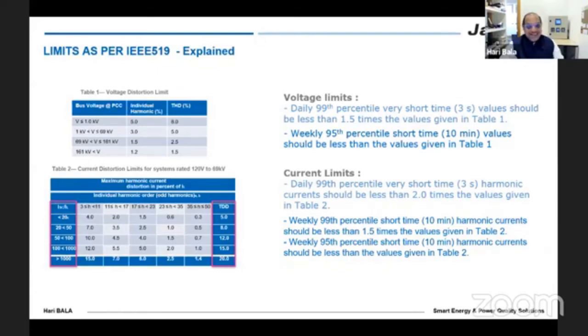This is one part of it. As I said, there is a three-way calculation: 99 percentile, weekly 99 and 95 percentile. For that, these limits have to be applied according to either 1.5 times the table value, one time the table value, or 2 times the table value. The table value is statistically evaluated according to the weekly or daily current limits. So it's a very complex process, how this whole thing works. I would say it's a very high challenge for everyone to do it.